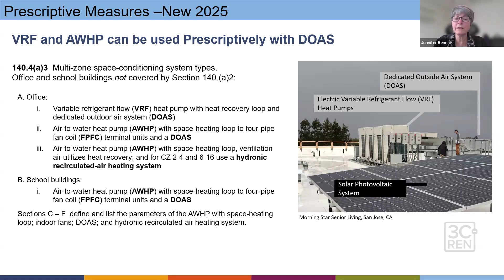Conceptually, for architects, you have one system — your dedicated outdoor air system — that may or may not include some heating and cooling, though in our mild climate zones often it doesn't. Then you'd have your VRF or air-to-water heat pump system that sends heating and cooling to your ducted air handlers inside the buildings.